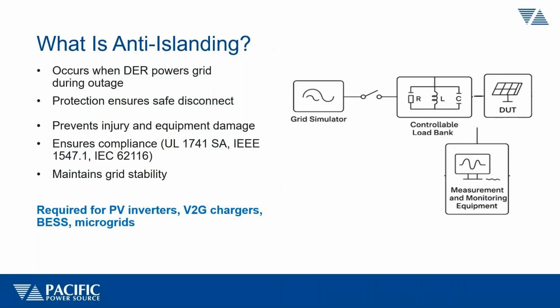So what does anti-islanding mean? It's really a mechanism that prevents the grid from being energized when there is a utility power failure. So when part of the grid de-energizes for whatever reason, could be natural disasters, could be storms, could be arcing somewhere in the grid, any DER, or distributed energy resource, that's connected to the grid and synchronizes to it has to be able to detect the disappearance of the grid connection and act accordingly by disconnecting, disengaging, and stopping putting power on that part of the grid, so that it's no longer energized.